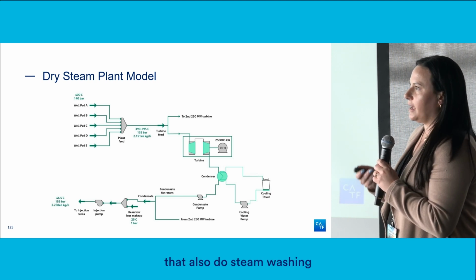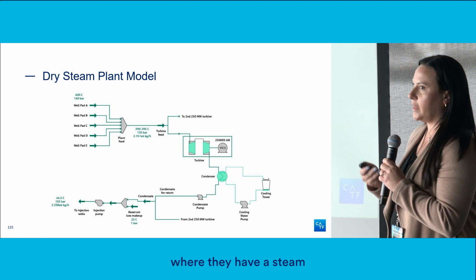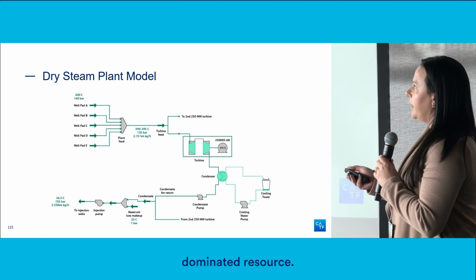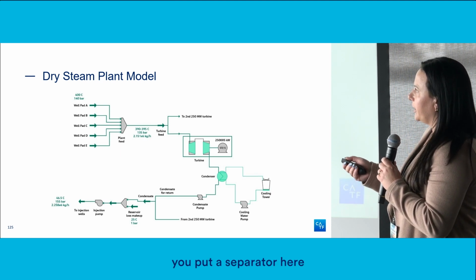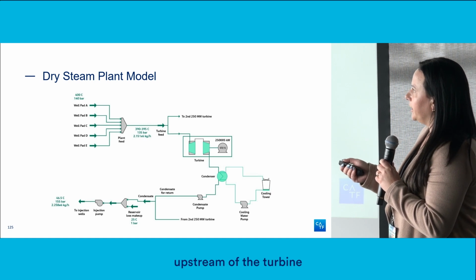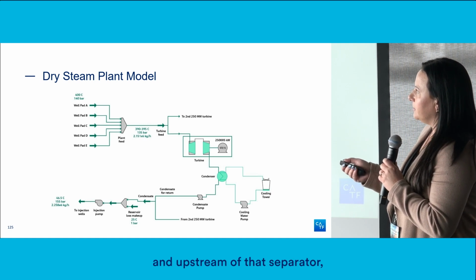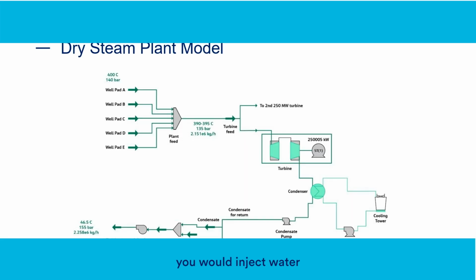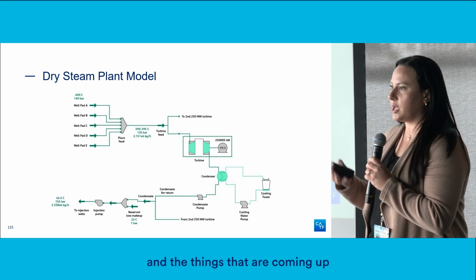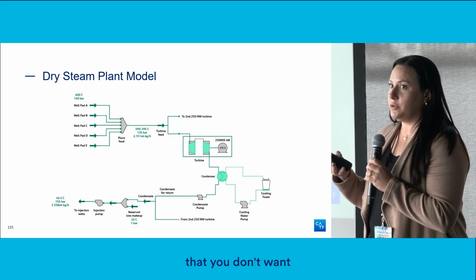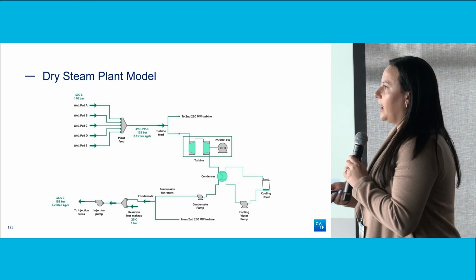There are other fields that also do steam washing where they have a steam-dominated resource. Essentially you put a separator upstream of the turbine, and upstream of that separator you would inject water, which would bring your superheated steam back down to saturation. What that does is create droplets that collect the chlorides and silica and other things coming up with the steam that you don't want going into your turbine.